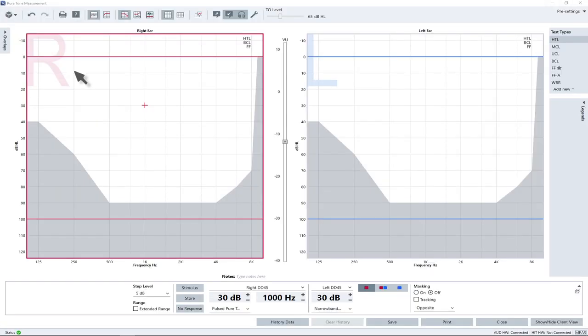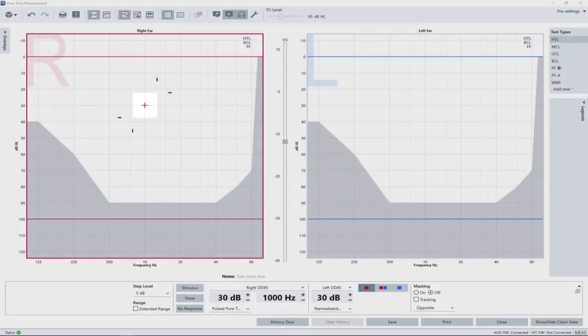The window opens with the default settings. In this example, the default point is at 30 decibel and 1000 Hz for the right ear. The curve type selected in default is the hearing threshold level measurement.